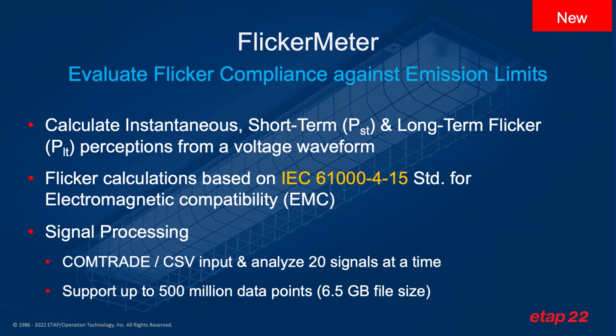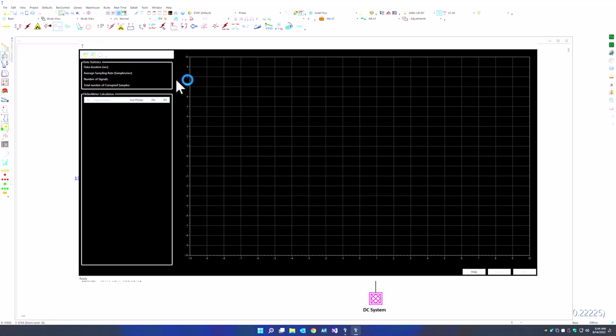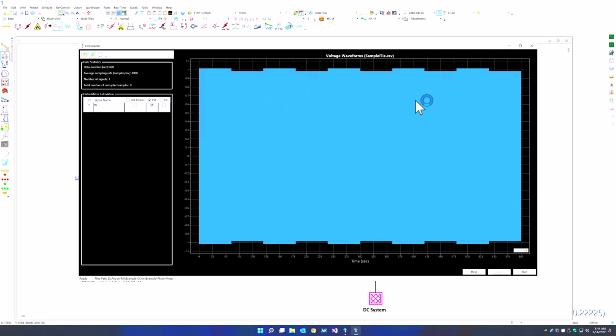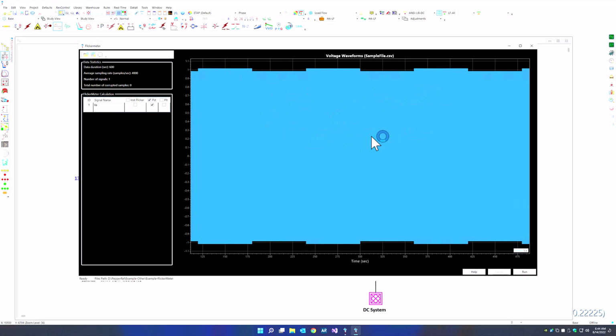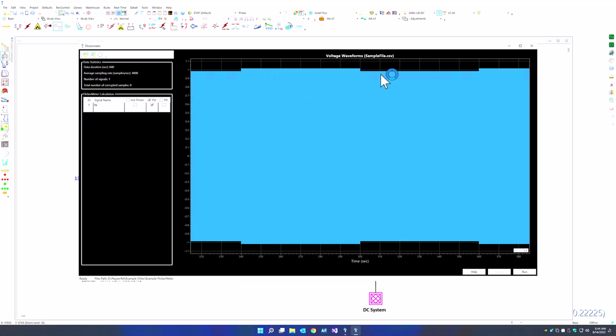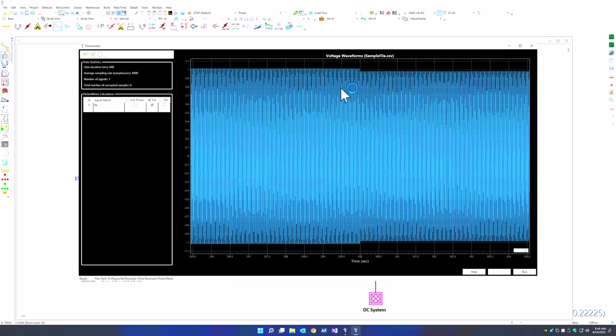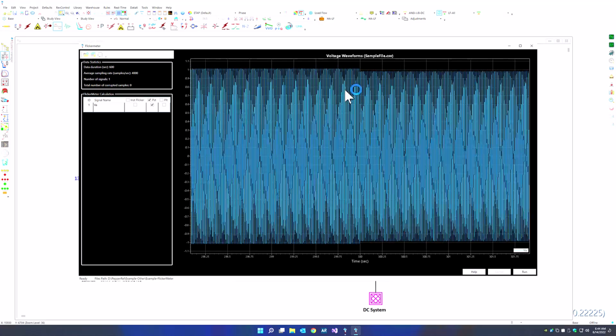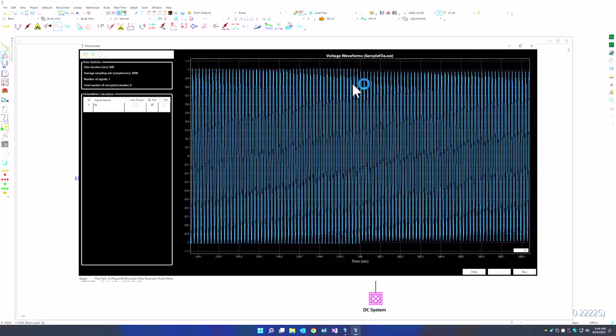And the purpose is to essentially determine the level of flicker in the voltage waveform based on various starting and stopping actions of equipment within a system, such as induction machines. We can launch the flicker meter, open up a CSV file, and the program very quickly loads that file into the plot so that we can actually zoom in and see the details of this particular waveform. You can use the control key and right click to essentially continue zooming into this diagram, and you can see our waveform emerging from all these data points that were read into the program very quickly and swiftly.